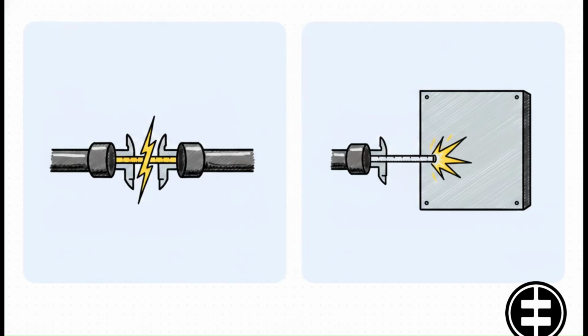As we all know, electricity loves to jump across gaps if you give it the chance. So, using strict IEC guidelines, testers meticulously measure clearances, which is the shortest distance in the air, and creepage distances, which is the shortest distance along the surface of an insulating material. They have to carefully distinguish between the space separating live parts with different polarities and the space between those live parts and exposed metal structural parts. Honestly, every single millimeter matters here to prevent a catastrophic arc flash.